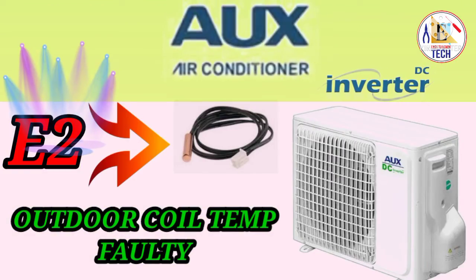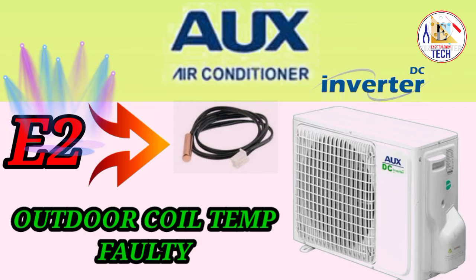Let's see the next error code. When you see E2 on your indoor display, it means your outdoor coil temperature sensor is faulty. Go directly to your outdoor unit and check the placement of your coil sensor. If the placement is not good, place it in the proper place. Then check the connection in your outdoor PCB. If the connection is loose, or if the wire between the PCB and the sensor is cut or damaged, you have to repair it and you will get the solution for the error E2.